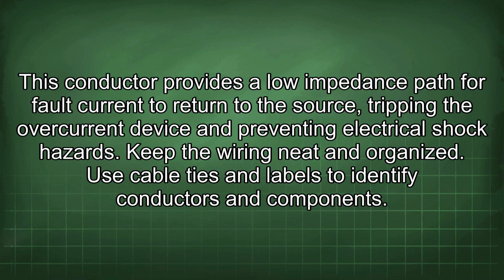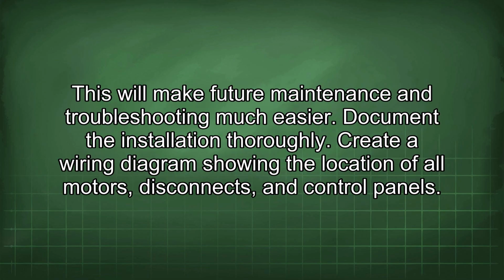250.122. This conductor provides a low impedance path for fault current to return to the source, tripping the overcurrent device and preventing electrical shock hazards. Keep the wiring neat and organized. Use cable ties and labels to identify conductors and components. This will make future maintenance and troubleshooting much easier.